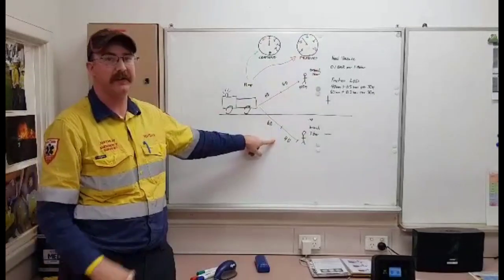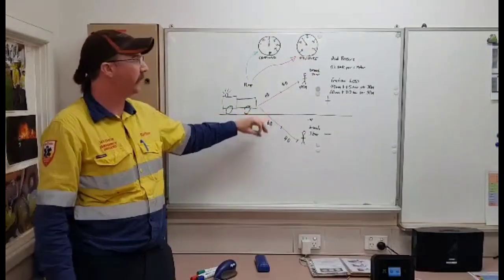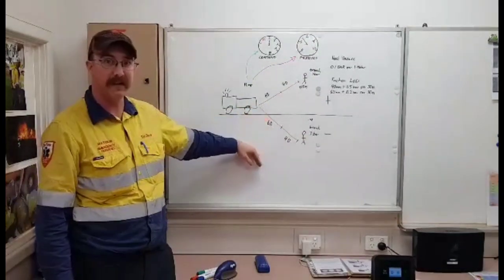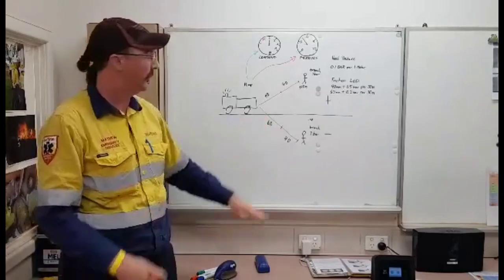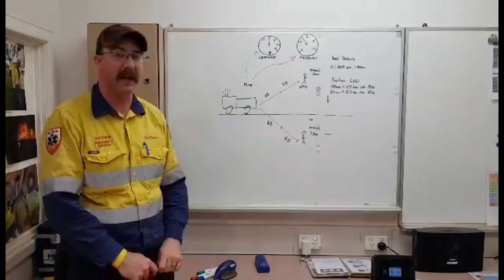We've got a little bit of friction loss so we're increasing, but then we also have that pressure of head negative. So we're minusing that extra 1 bar. So it's still 7 bar at the pump to get 7 bar at the branch.